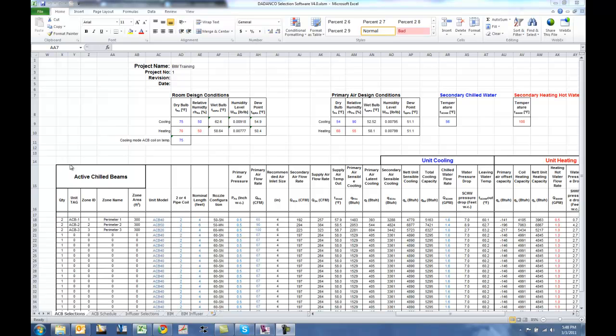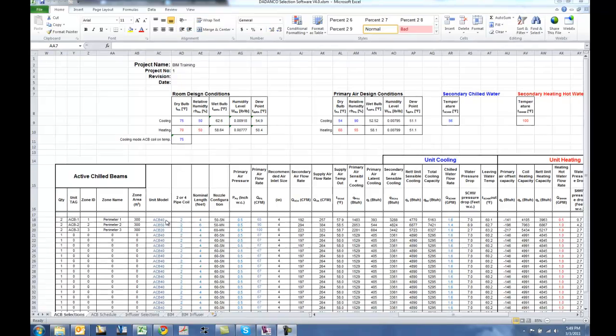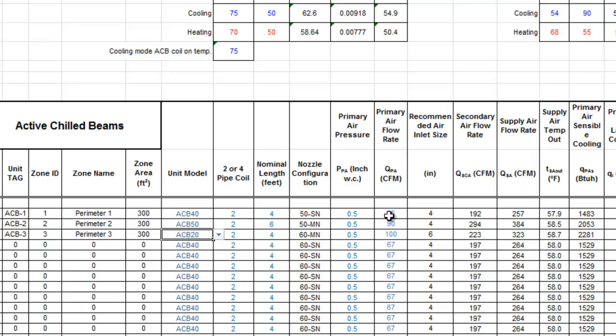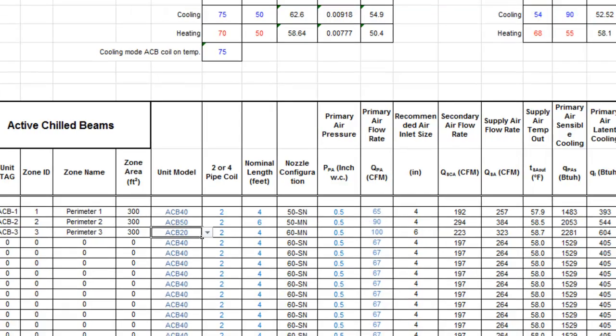So what we've done is we've created three different perimeter zones with this example, and within each of those three zones we've selected different models of active chilled beams. The first one has an ACB40, the second an ACB50 and the third an ACB20. Each of these three zones have different primary air flow rates, lengths of chilled beams and different water flow rates.